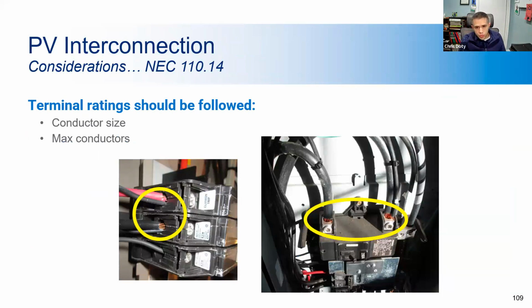Here you have terminal lugs where you land wires that are rated for conductor size and max number of conductors. These are rated for one conductor, and someone tried to sneak in a separate second conductor, which is against code. So here you see right over here, you see the main breaker where conductors have been doubled up, and here you just see breakers where they've been doubled up. So that is not allowed. You have to follow the requirements of each piece of equipment.